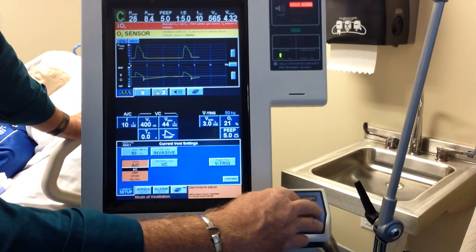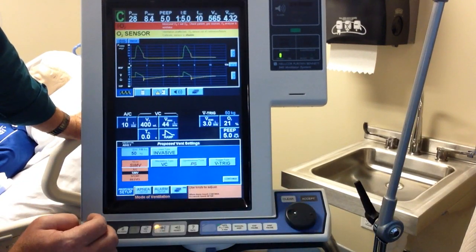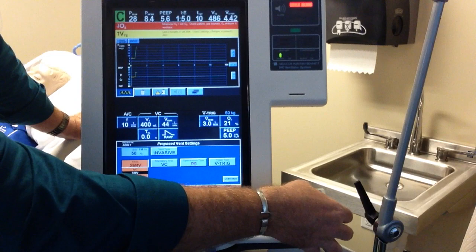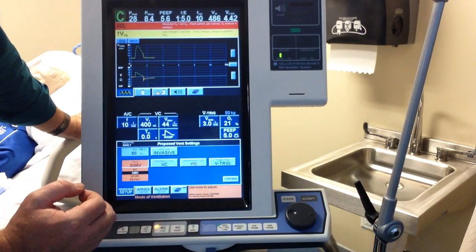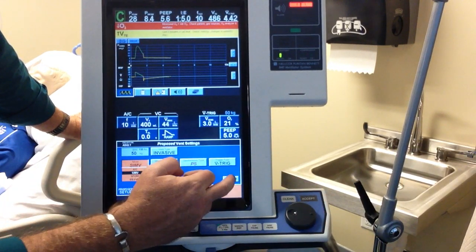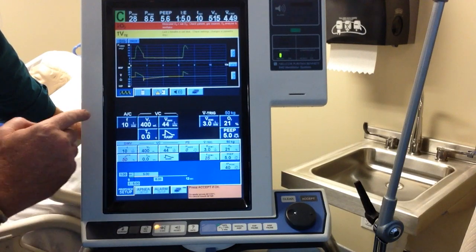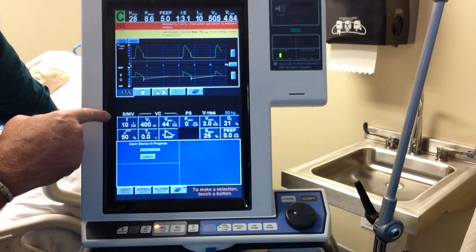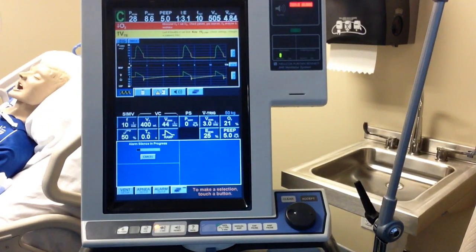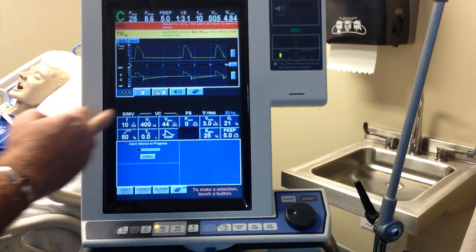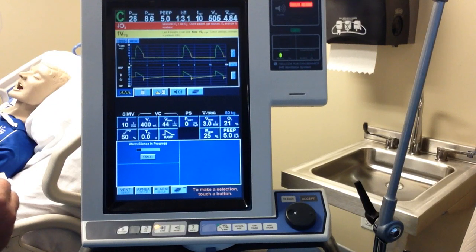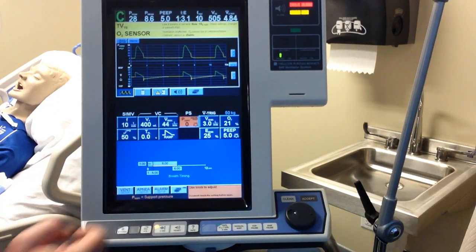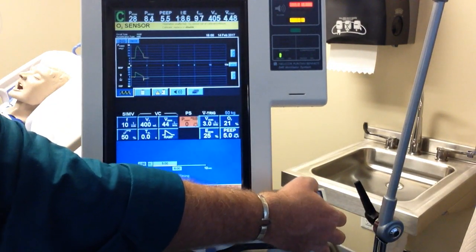I can go to AC, go to SIMV. I'm going to accept that. Continue. And these are my apnea. I have to accept. Now I have SIMV. If you notice my SIMV, all the settings are the same. Now I have pressure support.